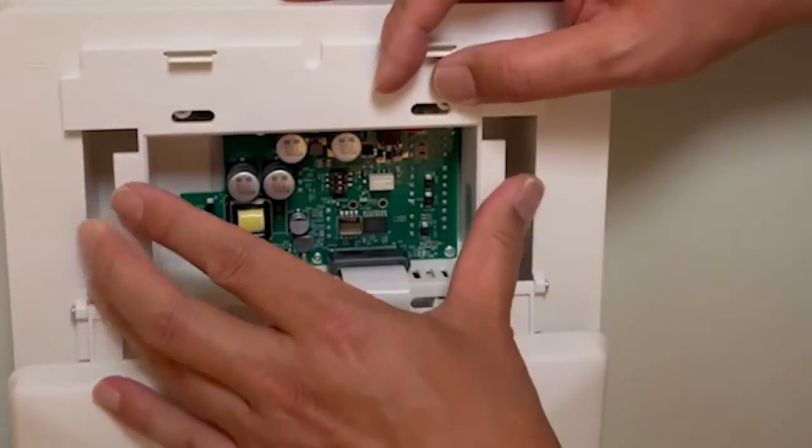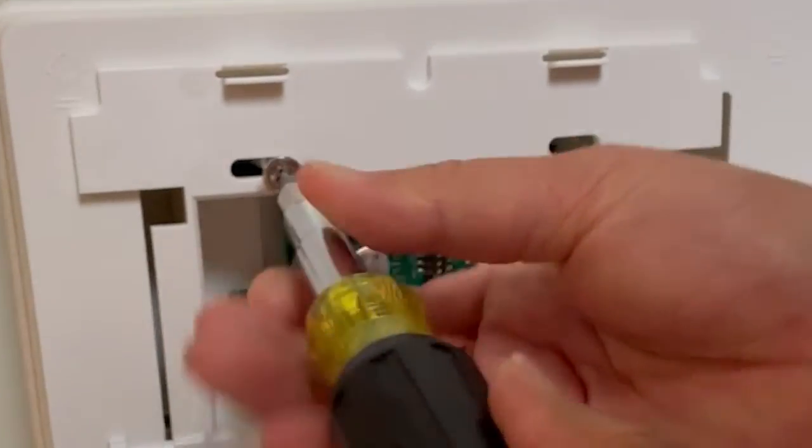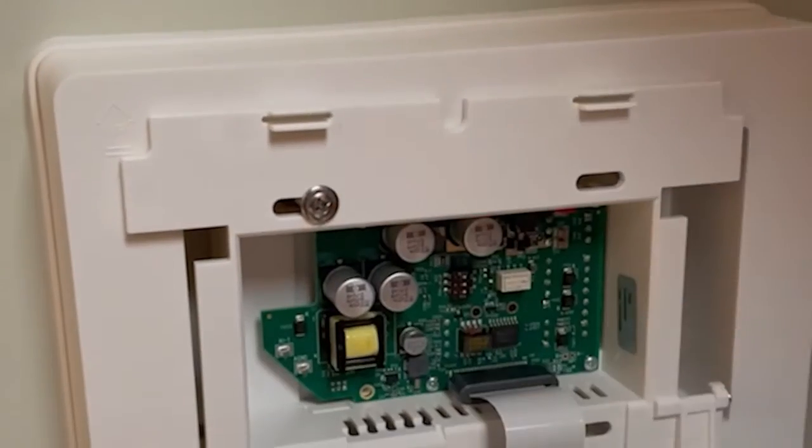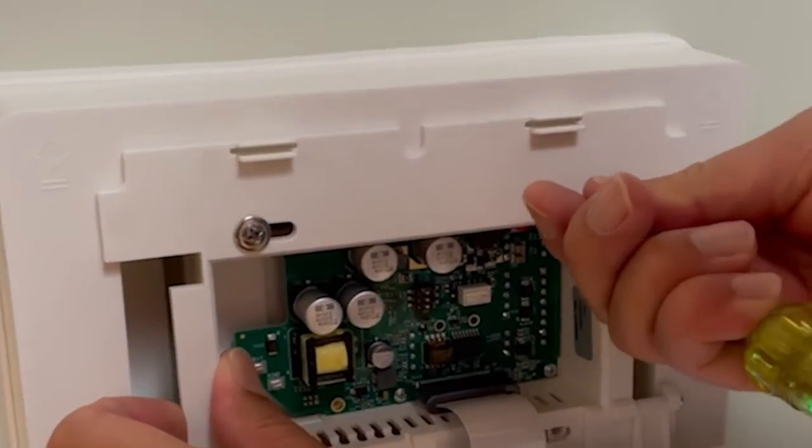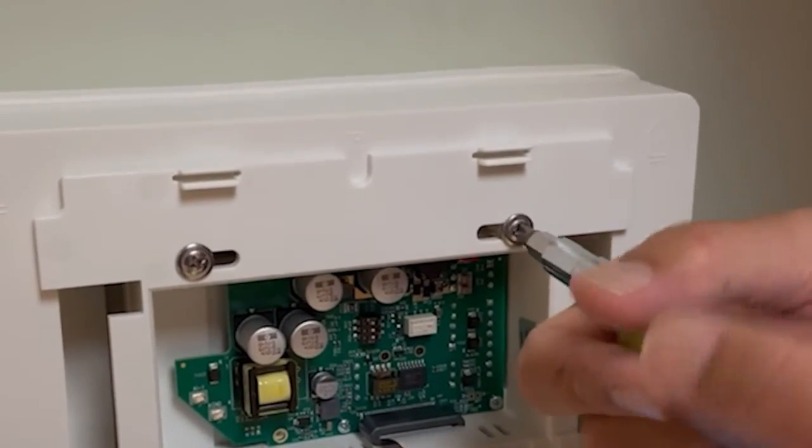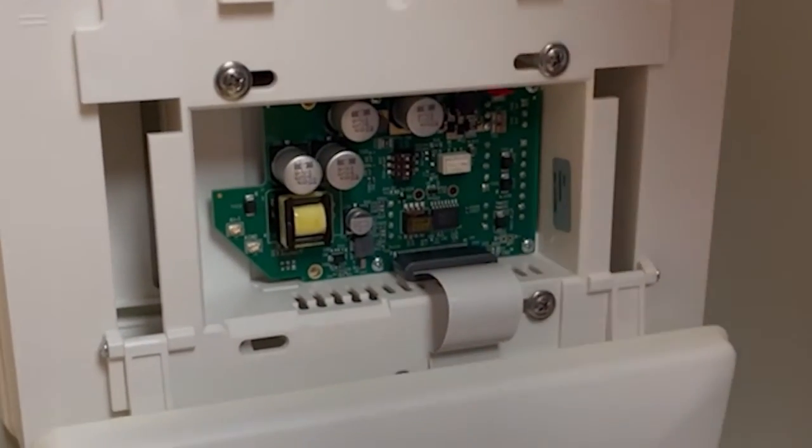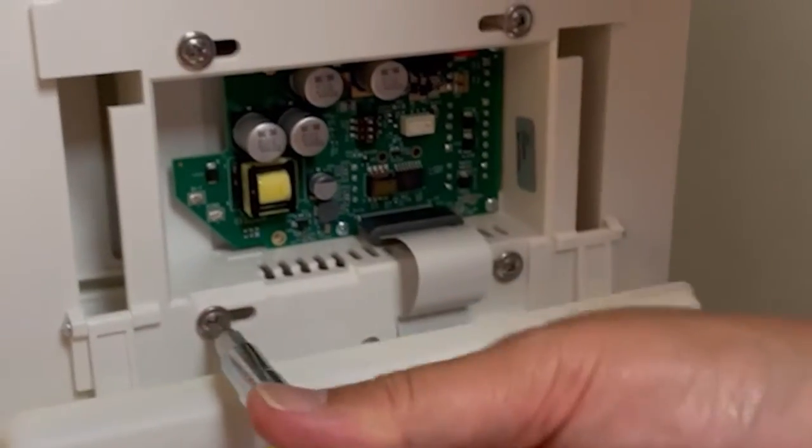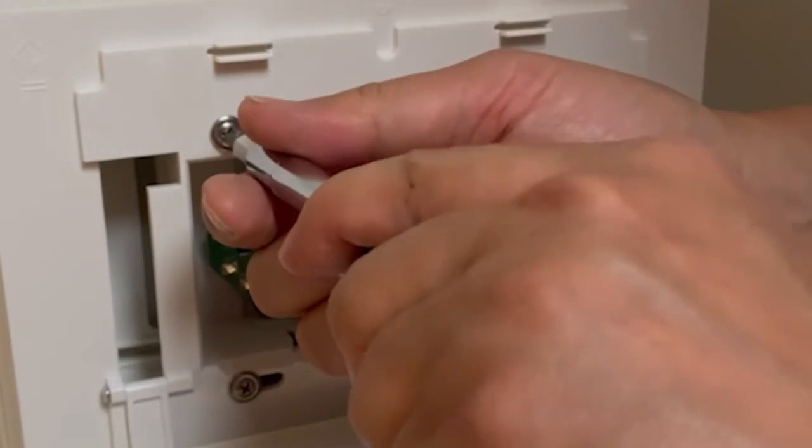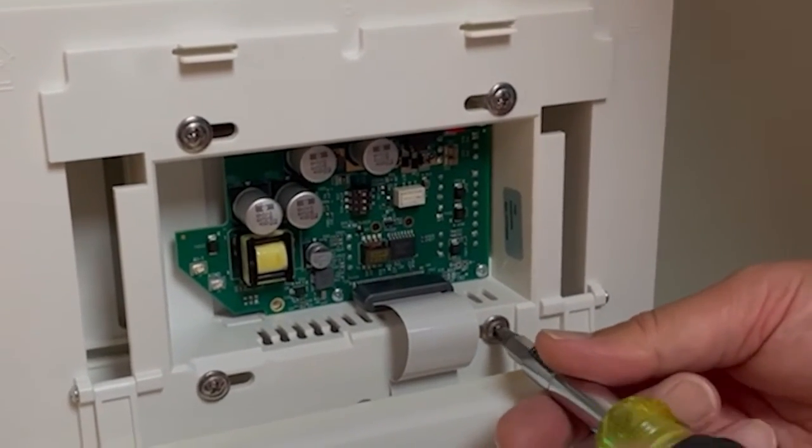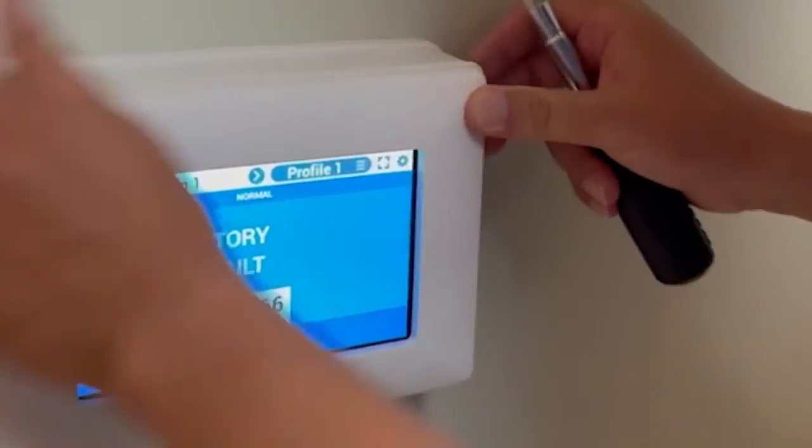Remove the faceplate of the CETRA off of the installation box. In your kit you're going to have four metal screws, about five-eighths inches long, self-tapping sheet metal screws for installing the box onto the extension ring. The spacing of the screw locations on the extension ring will center the monitor on the box on their own. Make sure everything's snug, then install your faceplate by pressing firmly at the four corners.